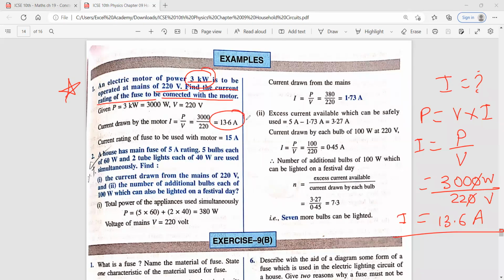The current will not exceed this amount, but the rating of the fuse must be slightly greater than 13.6. Now the fuse doesn't come in 13.8 or 14 or 14.5. The fuse comes after 13, it comes in 15. So you have to use the 15 ampere fuse, not less but slightly more.